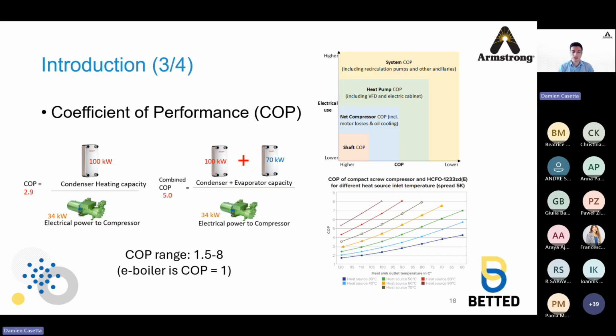But even more important is to understand that COP is not a constant value, and that it changes drastically with respect to boilers. It's not like 90, 95%, and that's it. No, it varies with temperatures, the temperatures that you get on the cooling side and on the heating side. You have some curves at the bottom right of the slide. You can have a look at the great variations, between 1.5 and 8. And the smaller the difference between the cooling and the heating side, the higher the COP gets. So between 1.5 and 8, and comparing to an e-boiler, which is 1, you can understand why it is more efficient.